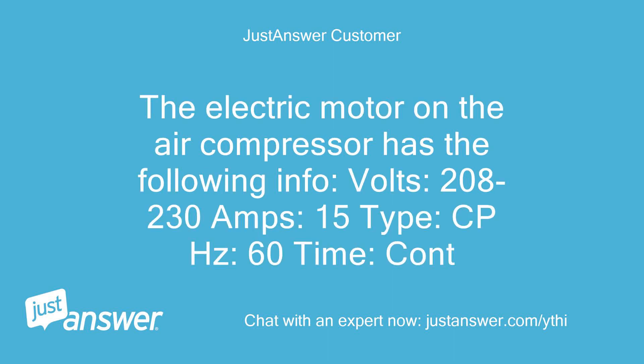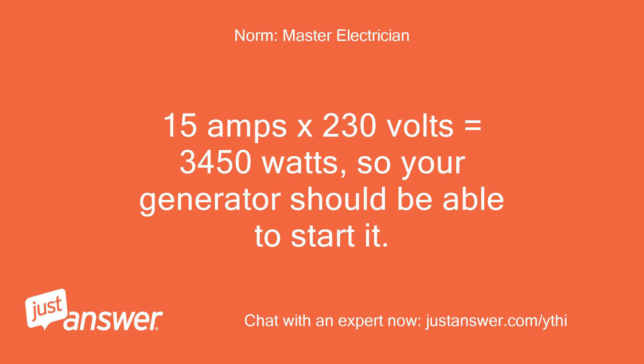The electric motor on the air compressor has the following info: 208 to 230 volts, 15 amps, type CP, 60 Hz, continuous. 15 amps × 230 volts equals 3,450 watts, so your generator should be able to start it.